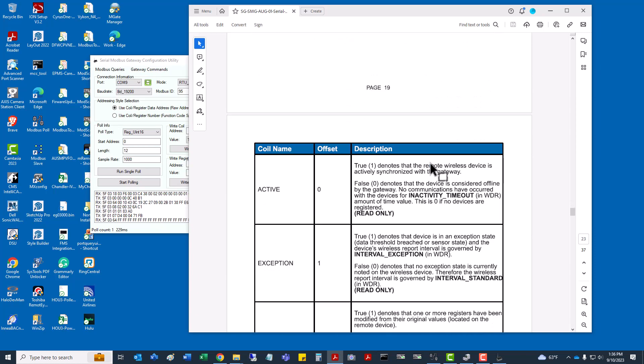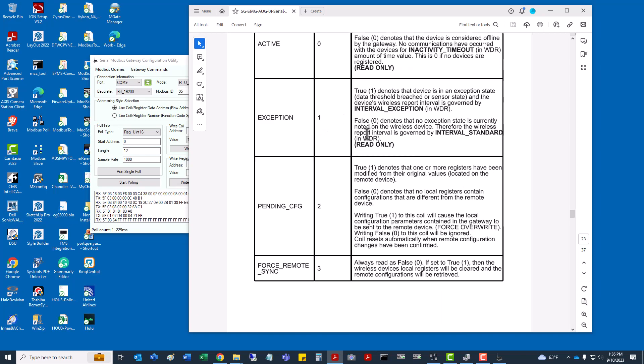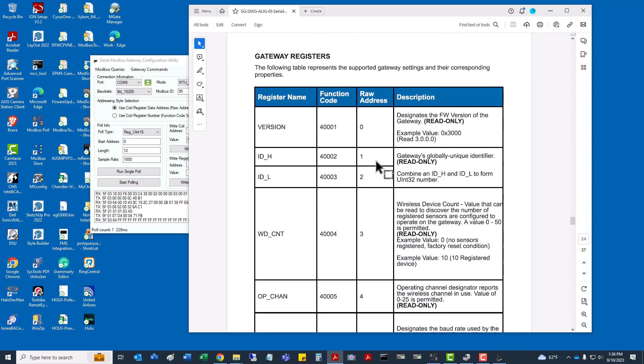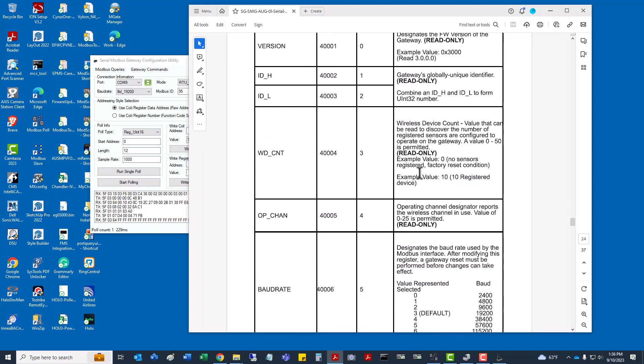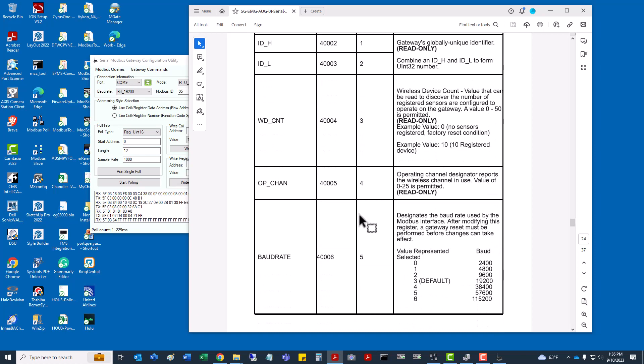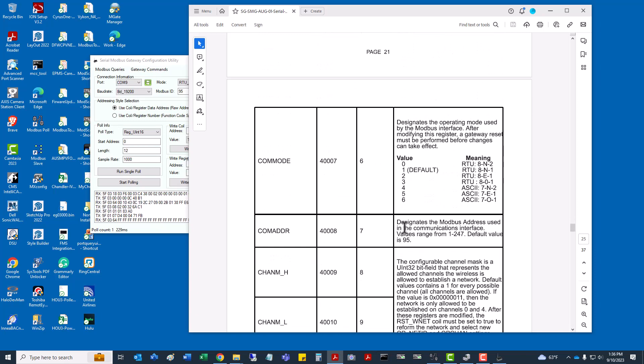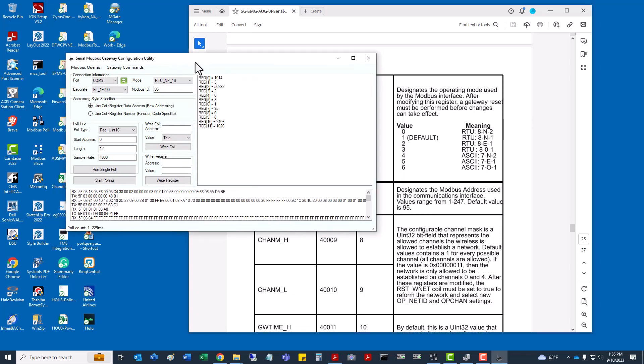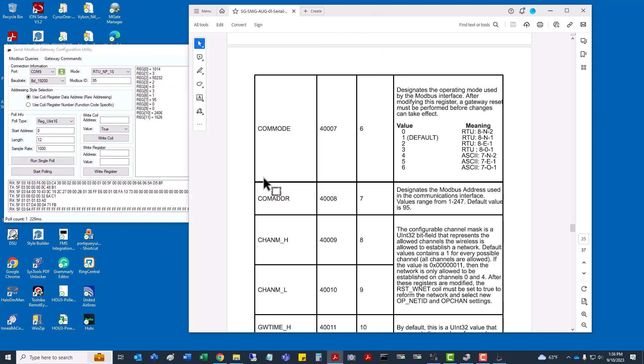I imagine you can write to that and change that over to whatever you need. I haven't tried to change mine yet. For the first few instances, I'm just going to keep it set to that default 95. There are the holding register sets: firmware version ID, some floats, different data points, the baud rate. You can read that in if required. Here it is, the comm address 40008. If we look at 40008, you can see that's coming over technically as address 7. That's coming in at 95. So here you should be able to write to this holding register and change it to something if you didn't want to use that default slave ID of 95.